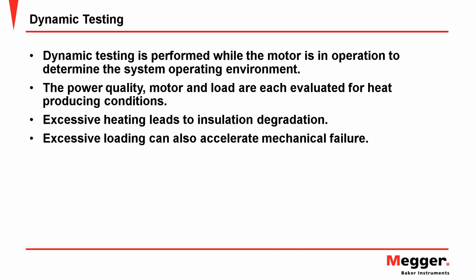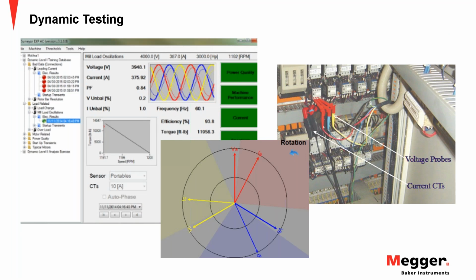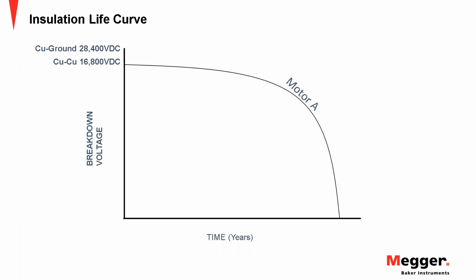Excessive loading can also accelerate mechanical failure. So in addition to heat, we also have mechanical stresses that are applied by increased load. So dynamic testing helps me, by looking at all these different parameters, by connecting the motor while it's running, I can evaluate the environment that's going to create heat or create additional mechanical stress, or even evaluate the actual condition of some of the mechanical components, which is a vital piece of understanding the system and what we can do to potentially improve the system and the environment that the motor has to live in.